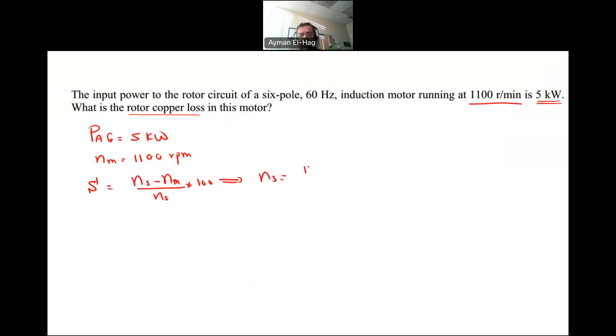So what is NS is equal to 120 times F divided by P, which is 120 times 60 divided the number of poles, which is here is 6. So this will give me 1200 RPM. And this is expected to be higher than NM. Always the synchronous speed is higher than NM. So from this, my S is equal to 1200 minus 1100 divided by 1200 and times 100. This will give me 8.33%.